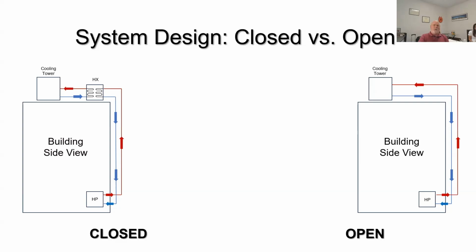Typically your cooling tower and heat exchangers are on the roof. So I've got to find a place that I can put another set of pumps, and then a lot of times, it's not abnormal if I have a 100-ton tower that my heat exchanger is going to be 9 to 10,000 pounds. And it's all going to be in a pretty compact footprint. So a lot of times on these older buildings, the structure of the building just simply can't take the weight of a heat exchanger.